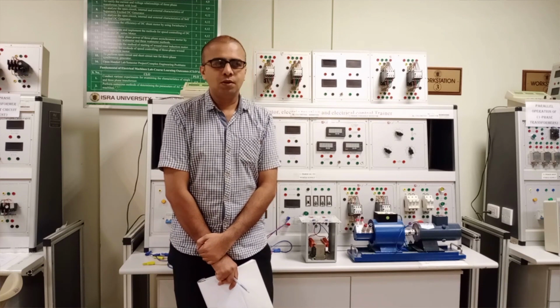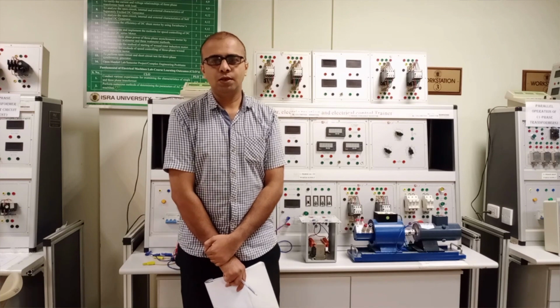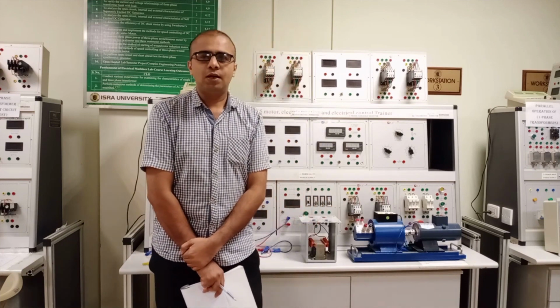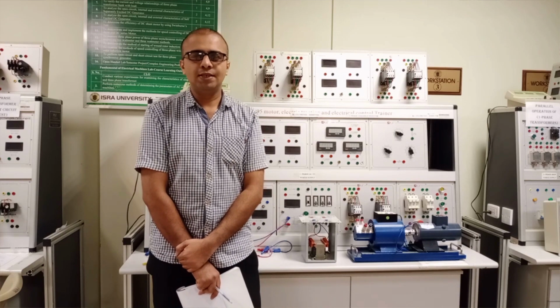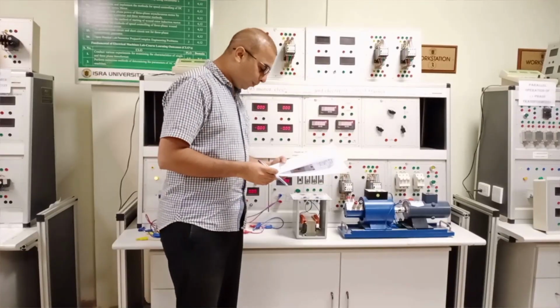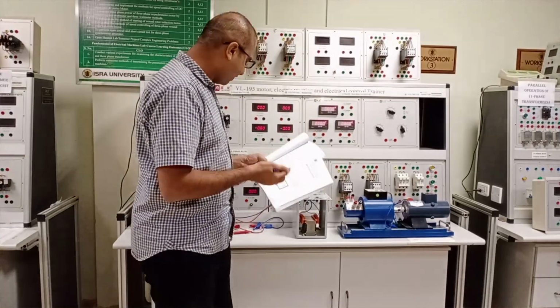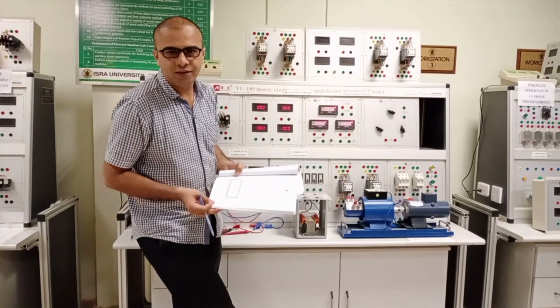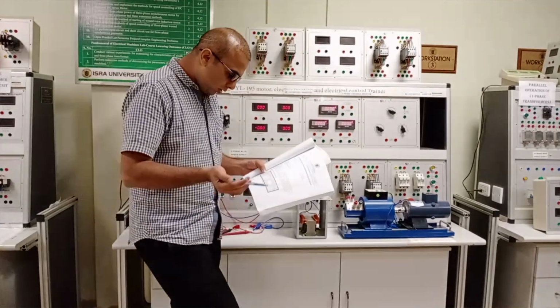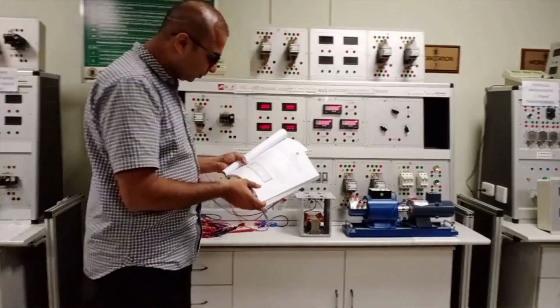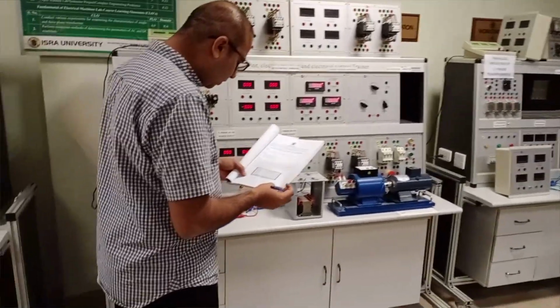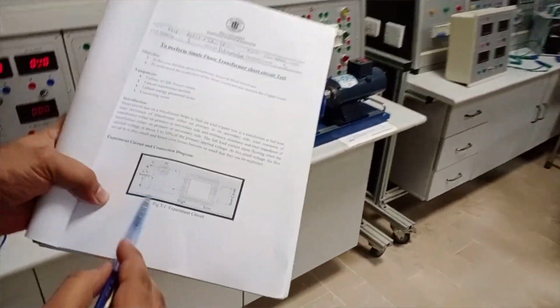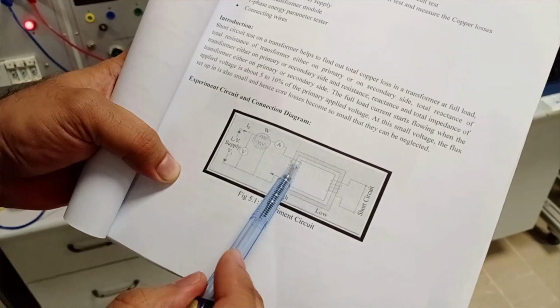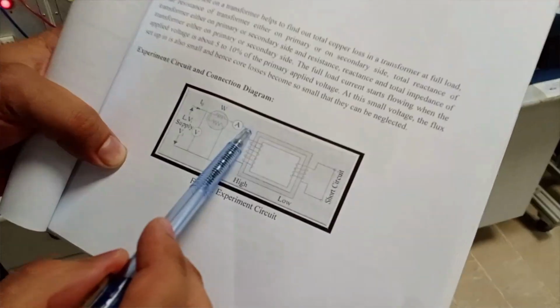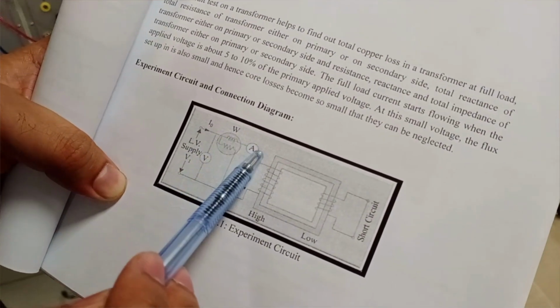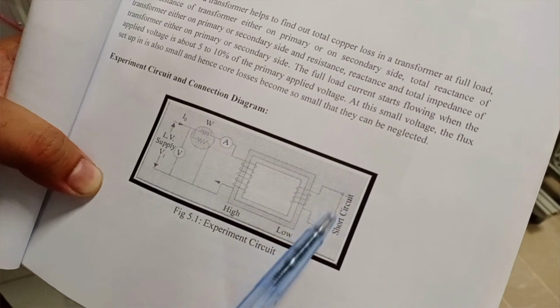According to the circuit diagram, the low voltage winding is kept short circuited and the high voltage winding of the transformer is energized from the AC supply. Now after that we have to understand this circuit diagram of the short circuit test that we have to perform on this panel. As you can see in this diagram, the high voltage winding is connected with the AC supply, and this is the wattmeter. And this low voltage winding is kept short circuited.